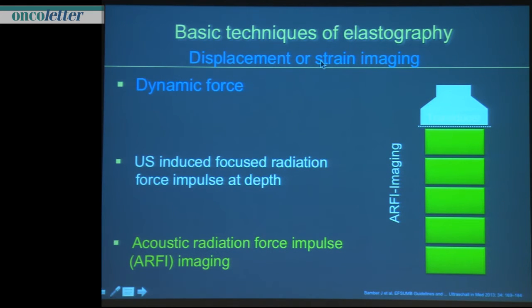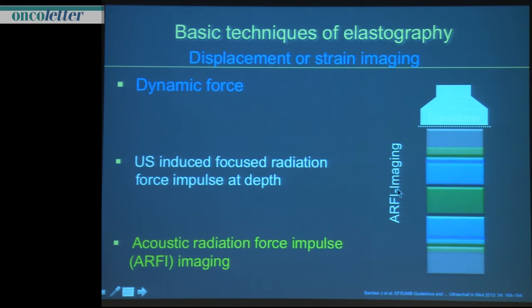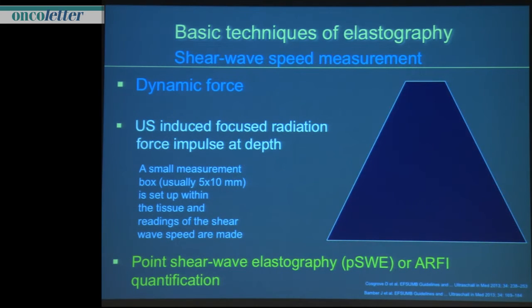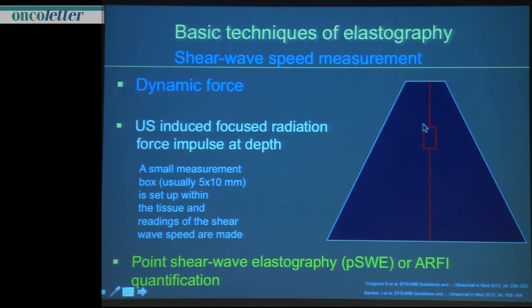The displacement can be performed using ARFI — acoustic radiation induced force. This force is used to calculate displacement, giving us a strain method but with an ARFI source of force. Now in shear wave speed measurement technology, we have one important point: a small measurement box, usually 5 by 10 millimeters. Applying the ultrasound push wave, the shear wave is measured within this box — so it's a single point of information.